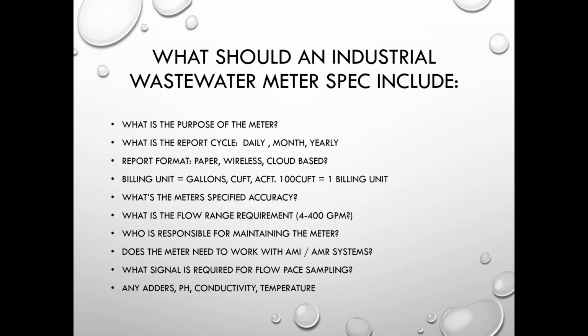What should an industrial wastewater meter spec include? A lot of times when I go to customers' facilities on the industrial side, I ask them, what is the requirement for the flow meter? And many times the answer is, well, I was told I have to have a flow meter. So I say, there are a lot of different styles of flow meters, and depending on what your requirements are, we'd like to nail that down and get you the best flow meter for that environment.